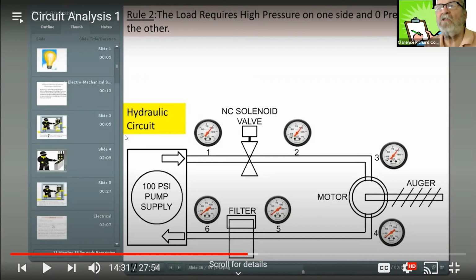The solenoid valve switch is turned on. The auger motor does not turn. Gauges 1 and 2 read 100. And my motor does not turn. The motor is bad. Restriction between 2 and 3. And yes, you guys, 100%. Very good. I'm impressed.